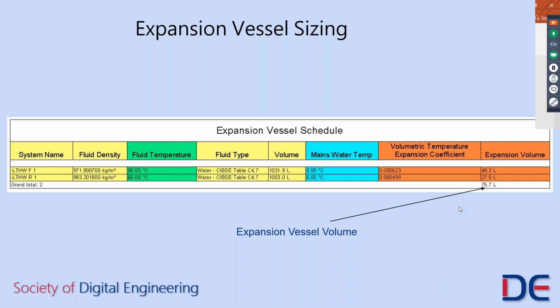As we extend our system to go throughout our building, or as we modify it according to whatever design is required, this will constantly recalculate, so we can always see if our expansion vessel is of adequate size. We can then actually build this in to our template. So every time we create LTHW or chilled water systems or any other pipework systems, we can calculate the expansion vessel volume on the fly.